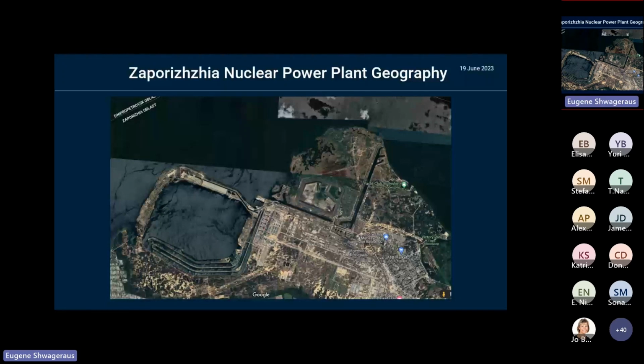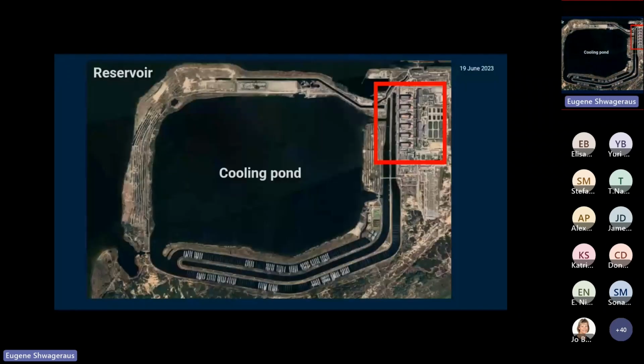These cooling towers are available and working all the time. The only time they're not needed is in the depth of winter, when ambient temperatures drop below minus 10 degrees. Then all six units can be cooled through cooling ponds without the cooling towers. So cooling towers are much more efficient but more expensive, and those sprinklers are very cheap but not as efficient.